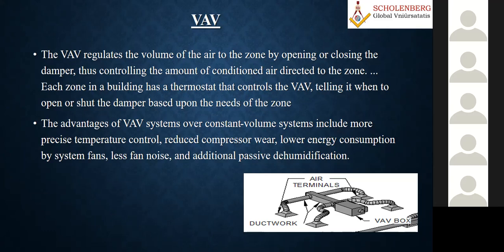If you see in olden days, there were only loaders, like bypass loaders. If it is a reciprocating compressor, there will be 4 or 6 cylinders, just like our car IC engines. Depending upon the chilled water temperature, this loading and unloading of the cylinders was done. Old days I'm talking about. Nowadays, that has all gone, and it had many disadvantages. That is why these sophisticated controls have started, even for centrifugal compressors of bigger size. So this will definitely allow us to save energy.